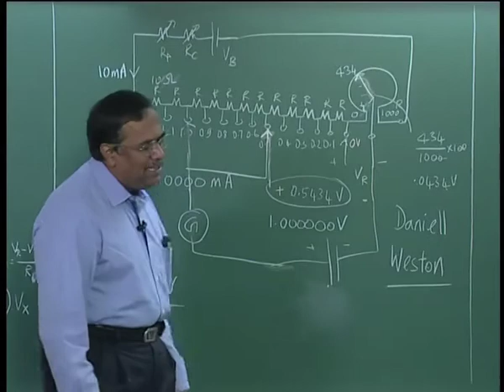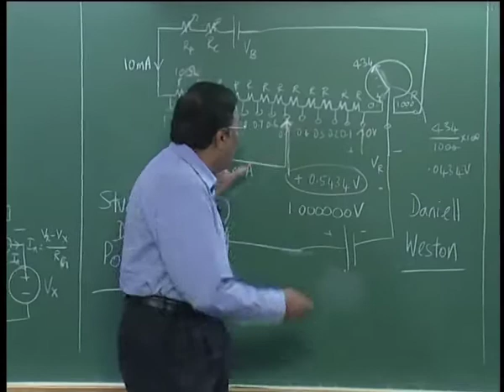So that was the standard cell that was used, and in the yesteryears the potentiometers had automatic tap off points to get this 1.018623 volts. You do not have to move your dials to get 1.018623 volts. The manufacturer would have taken out those points and kept them ready for you to connect your standard cell and make a standardization of the potentiometer. Normally on the DC potentiometer you have one switch which you put on standardization, where the DC standard cell is automatically connected, and you adjust the coarse and fine resistors, standardize, and then go to measurement.